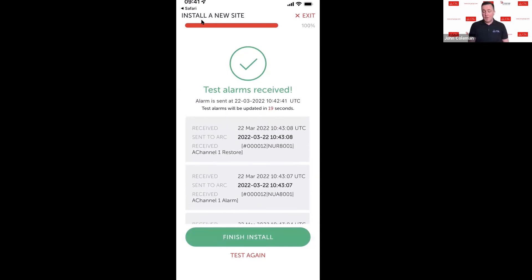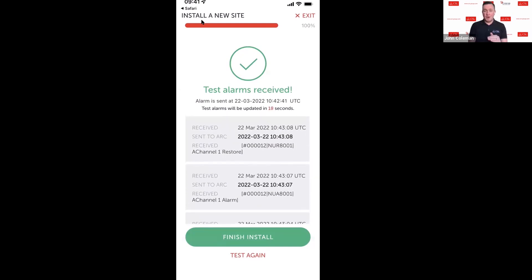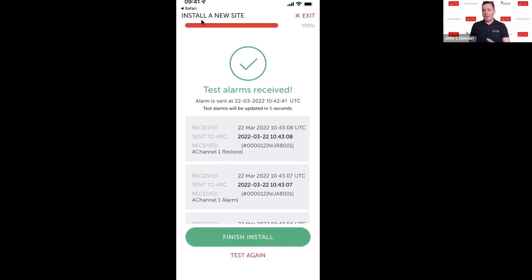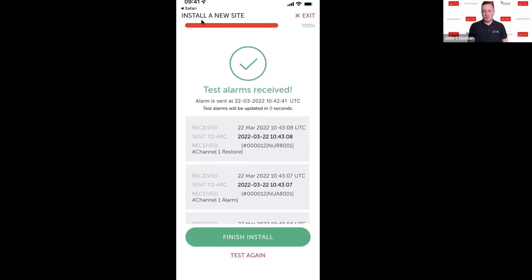Quite important at this point is that this process doesn't mean that you don't check with the ARC. You've still got to confirm with the monitoring station that they've received the alarms that you triggered. You want to make sure that you commission your site correctly. What we're seeing here is that the alarms are hitting our platform and getting delivered through to the monitoring station, but please ensure that you contact your monitoring station to ensure that those alarms have gone through correctly.